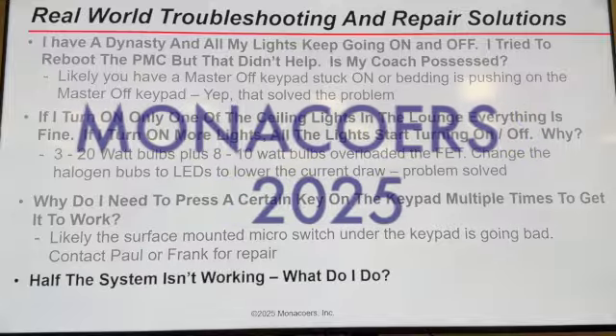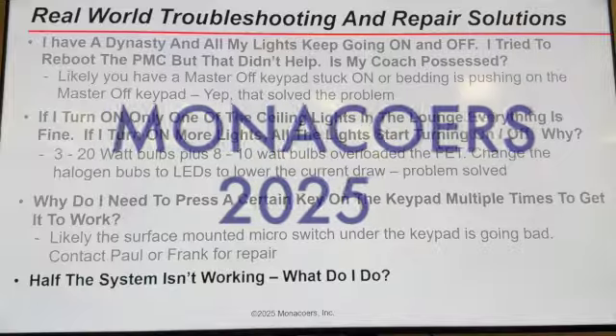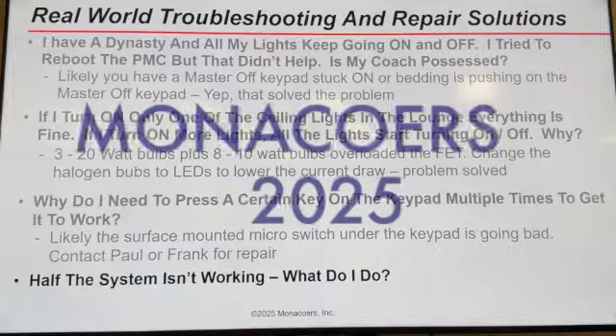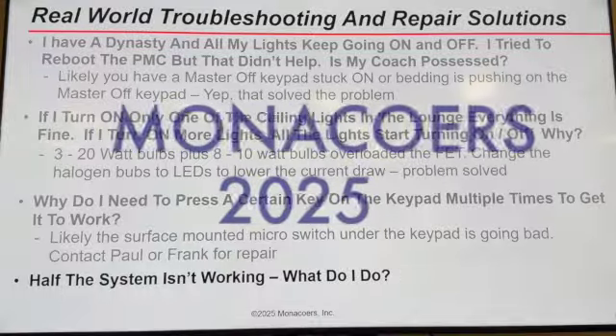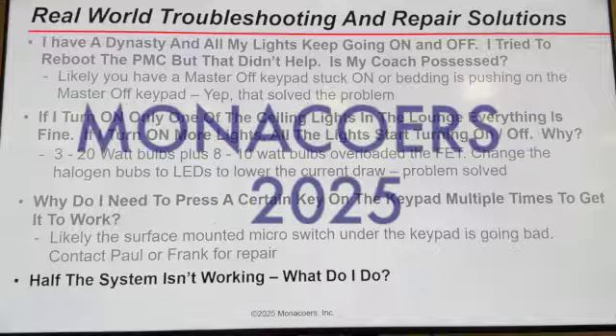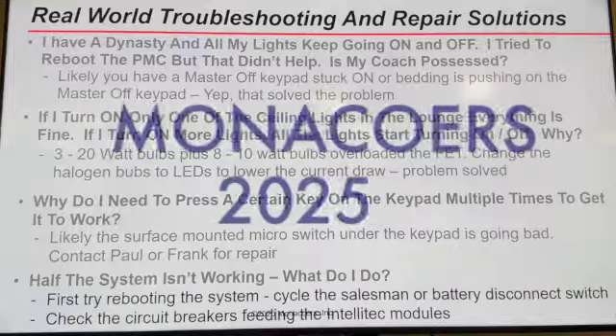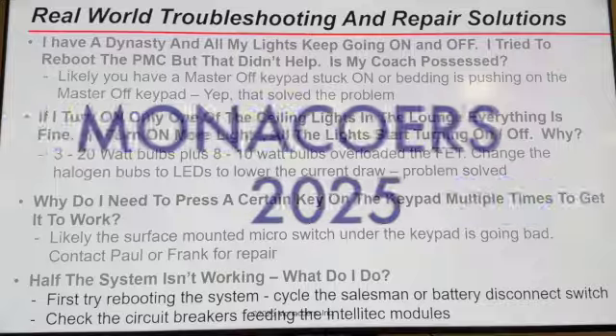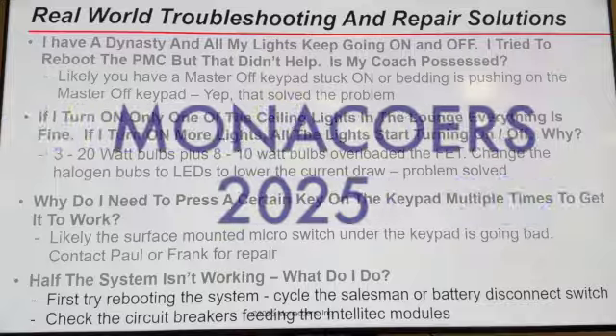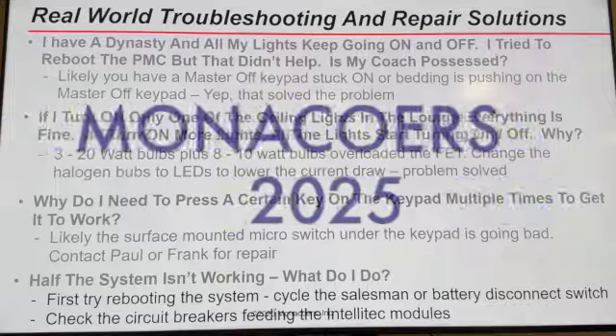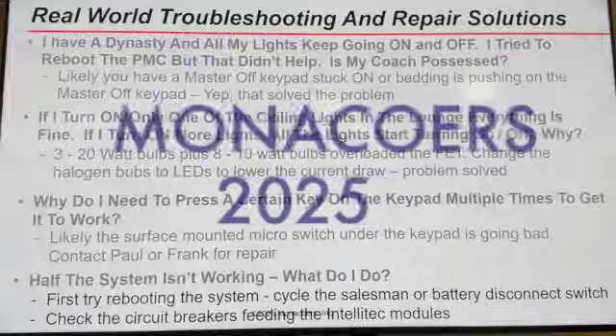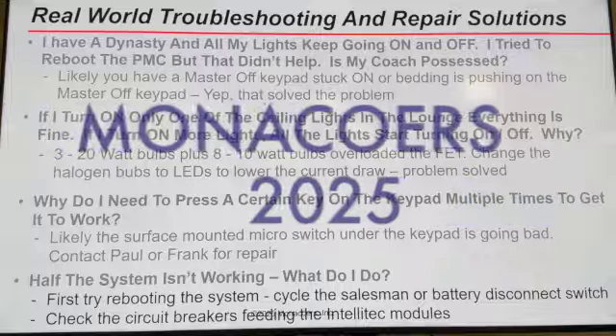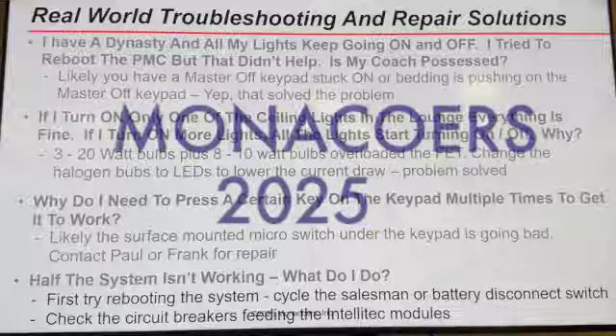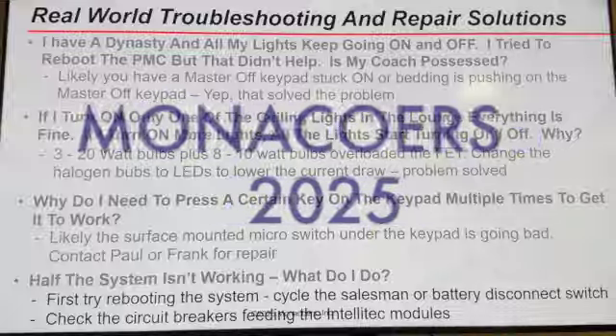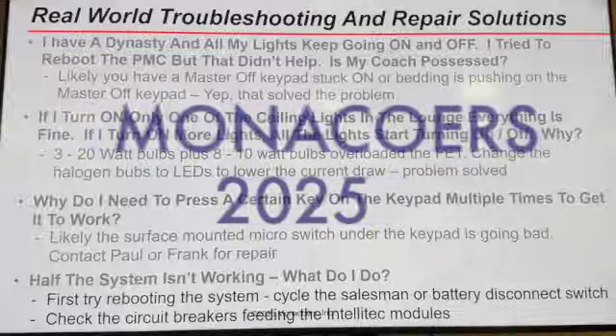Okay, half the system is working, or isn't working. What do I do? Anybody want to take that one? No? All right, first try to reboot the system, cycling the salesman switch or the battery disconnect switch, then check the circuit breakers feeding the individual Intellitec modules, because one or two of them may have tripped.